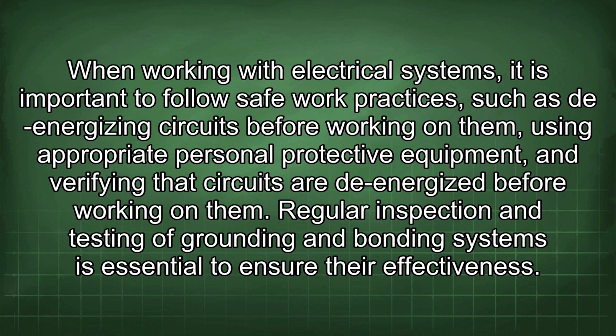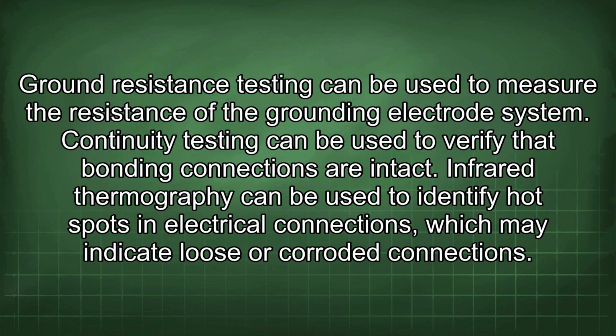Regular inspection and testing of grounding and bonding systems is essential to ensure their effectiveness. Ground resistance testing can be used to measure the resistance of the grounding electrode system. Continuity testing can be used to verify that bonding connections are intact. Infrared thermography can be used to identify hot spots in electrical connections, which may indicate loose or corroded connections.